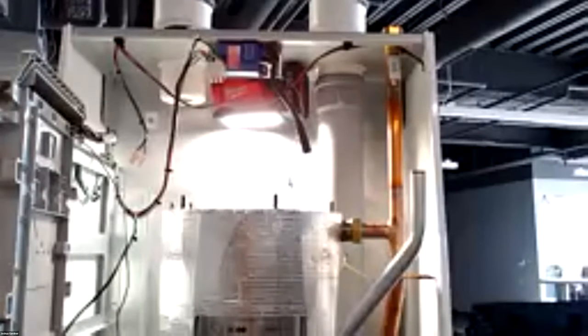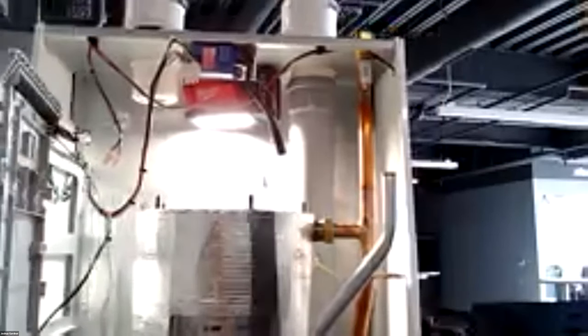Check your flame signal, make sure that's still strong. I change the igniter every couple of years at least. The burner head, we want to inspect, make sure that looks good. So I can turn this down.